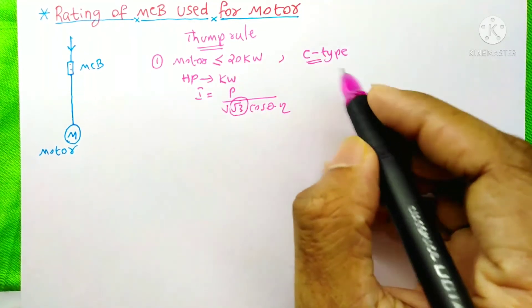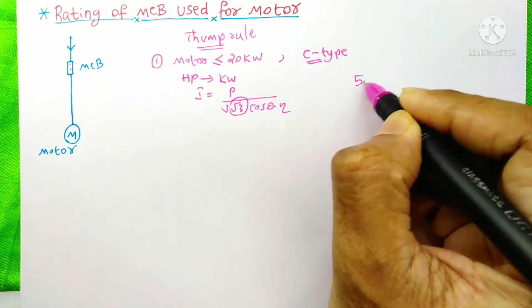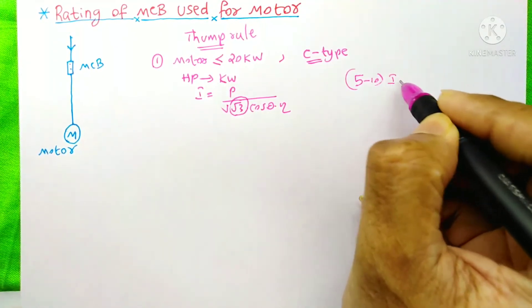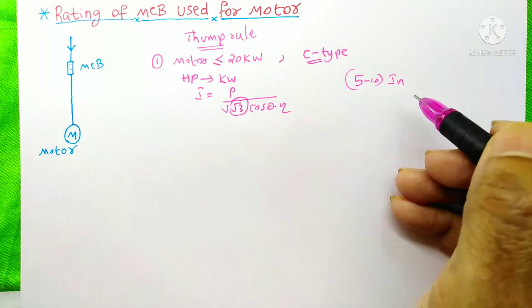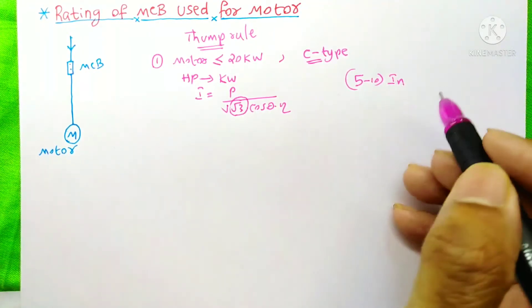This C-type MCB will allow 5 to 10 times of the rated current for a short time, maybe for one to three seconds.